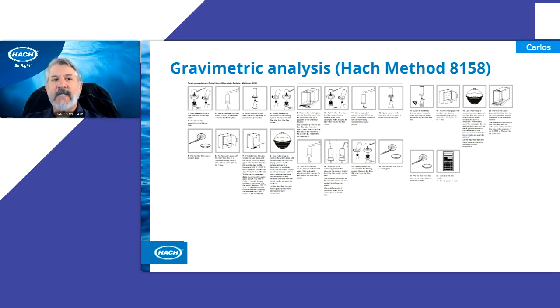But this is basically all the steps it takes to go through a standard gravimetric analysis. Essentially what you do, I kind of sketched it out already, you filter a sample, you filter a certain volume, you make sure that the filter element has been dried in an oven, then you make sure you have a constant weight once you dry it down. Then you measure the difference between the dry filter that doesn't have any solids collected on it, and then after the solids have been collected on it and dried. So there's a lot of steps to it. This is the entire point. And this is why measuring something online for total suspended solids is a lot better and a lot easier.